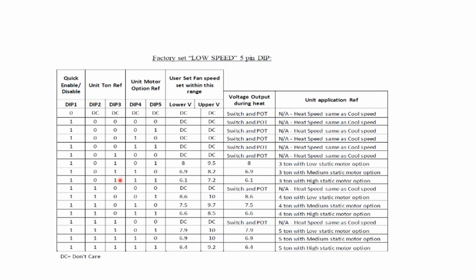2 and 3, like I mentioned, tell the board what tonnage unit it is, and then 4 and 5 tell the board what motor option you have. So do I have a low static motor option on a 3-ton unit? Do I have a medium static motor option or a high static motor option on a 3-ton unit? Same thing down here with the 4-ton as well as the 5-ton. So that's basically what these switches do. It will also give you voltage output during heating. Here it's either the ABC switch and the potentiometer setting. You get down here, and with this setup, this is the output you're going to have to the motor, respectively. Same thing with the 4-ton and the 5-ton. So it's just that simple. Any questions on that?